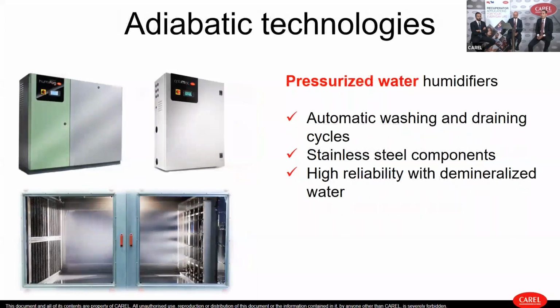An alternative can be adiabatic technology. Using pressurized water humidifiers, we can reach the hygienic targets for AHUs if these adiabatic technologies are equipped with an automatic washing and draining cycle for the distribution systems. All the components have to be provided in material like stainless steel, and using demineralized water, we can guarantee high reliability of the system.